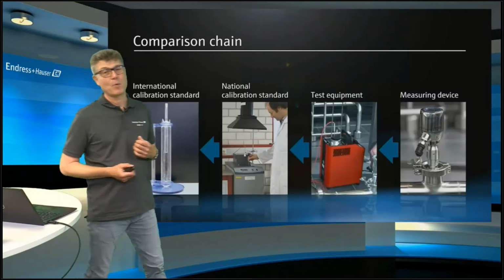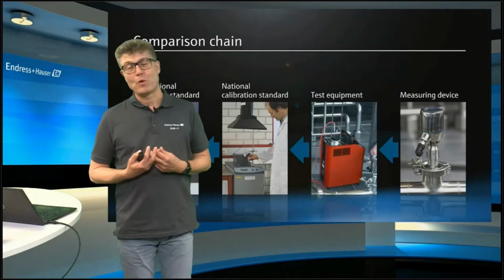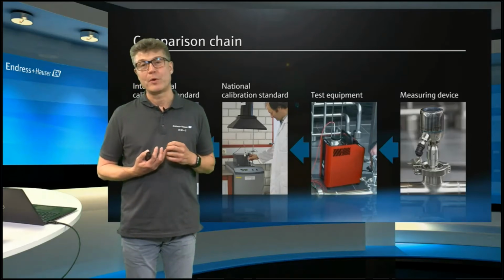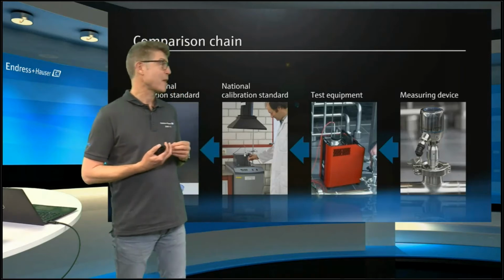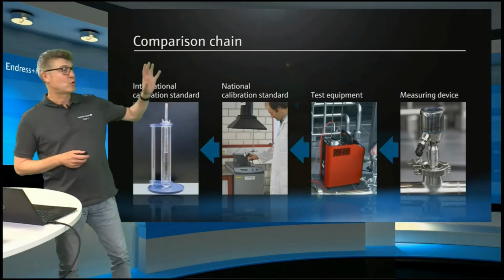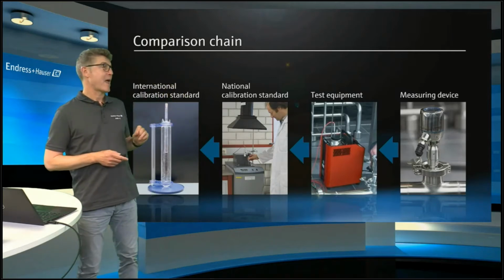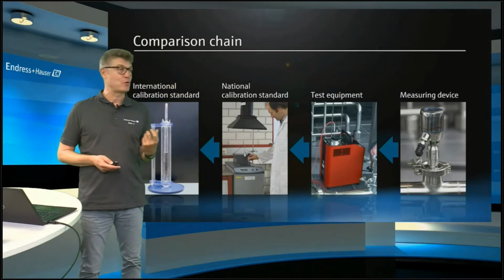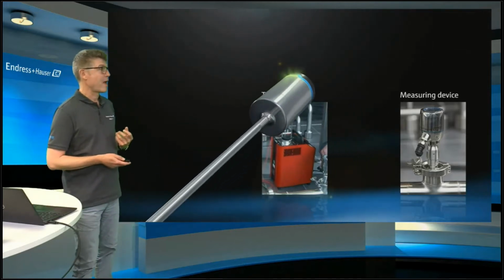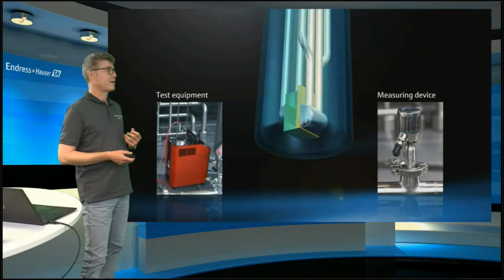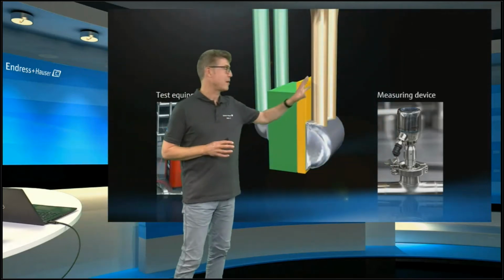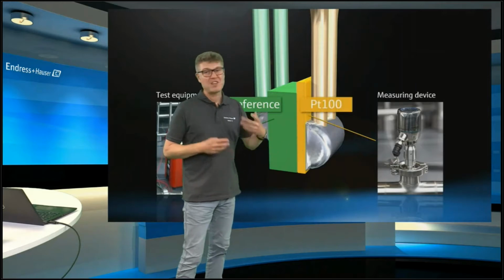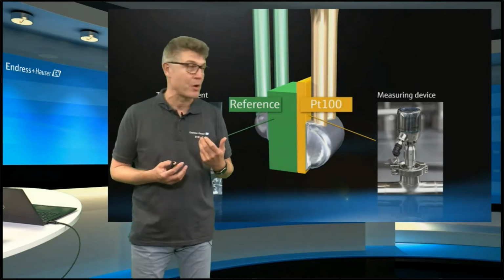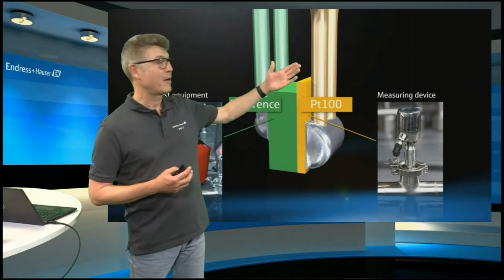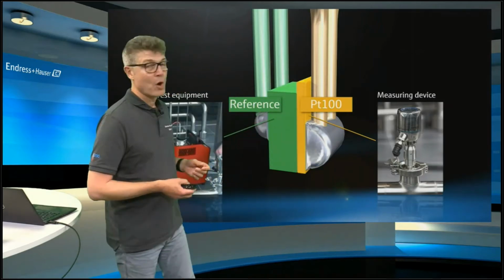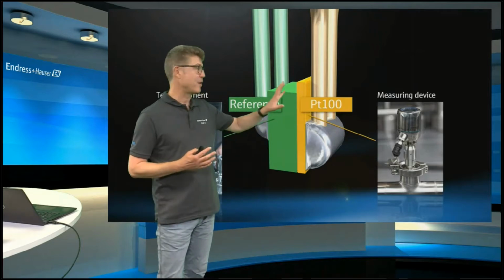So the general idea was to help our customers reduce the risk and save time and money. To do this, we took the traceability chain and built the lab into the sensor. We have a PT100, the industry standard for temperature measurement, installed in the sensor tip. Known and usual. But at the back of it, there is a reference.